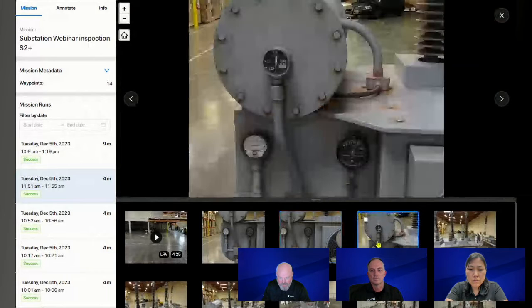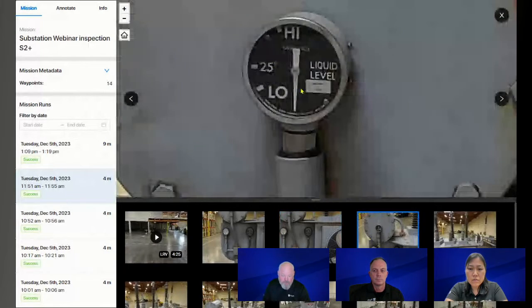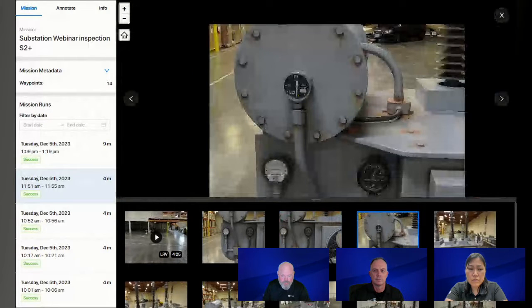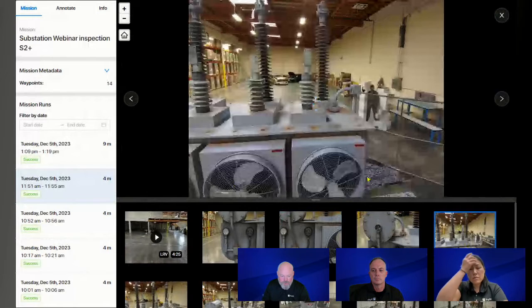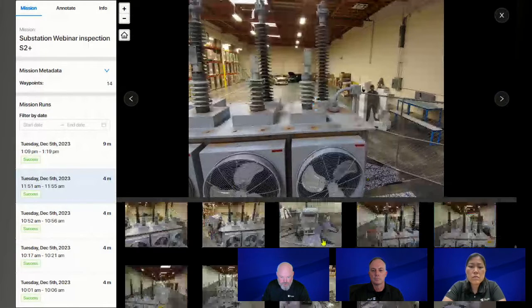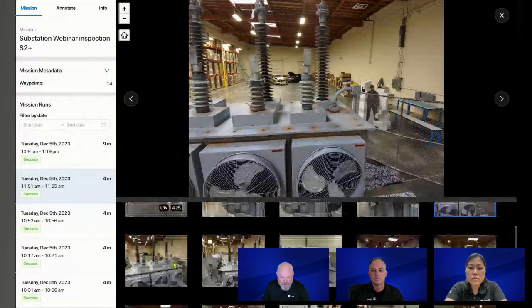We saw as we did our inspection live that our liquid level gauge is low, and our fans aren't running, when in most situations the fans should be running. We also found a chipped insulator bushing on our low side bushing for the power transformer. So we'll go back and look at that photo real quick.